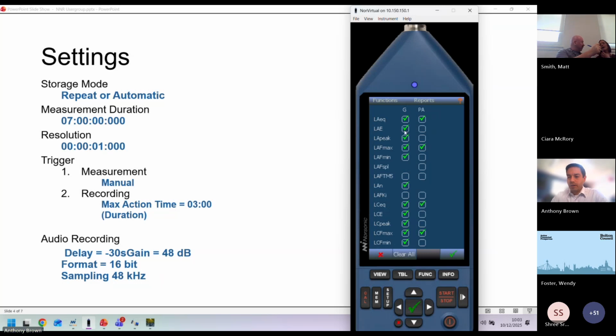Don't worry too much about all these ticks here, but you do need to make sure that the top one is enabled at least. So the LAEQ needs a tick under the G and then a tick under the PA. Just those 2 are the most important. That just tells the meter to save this data to the memory card. There's nothing more than that you need to know about.